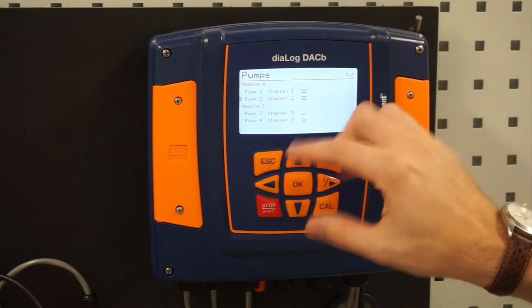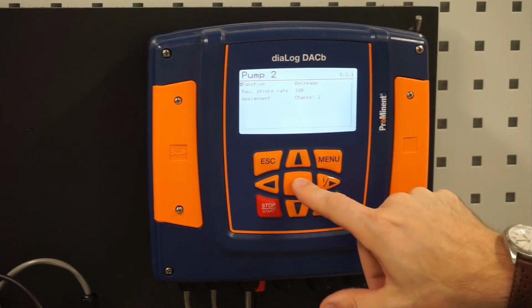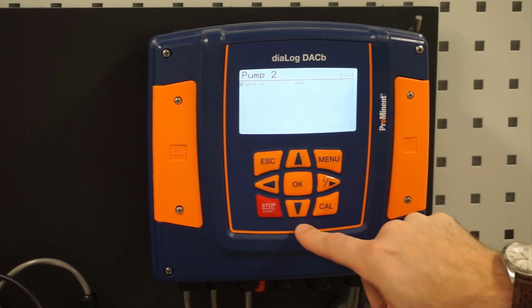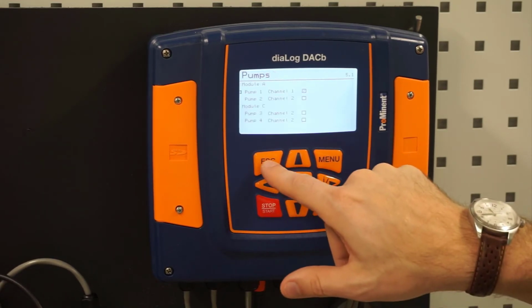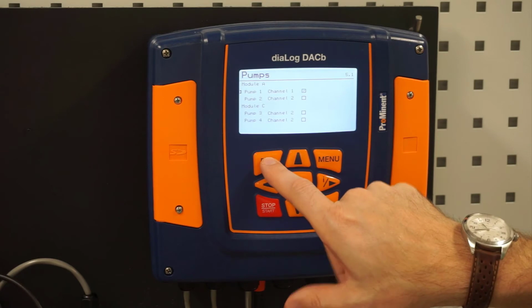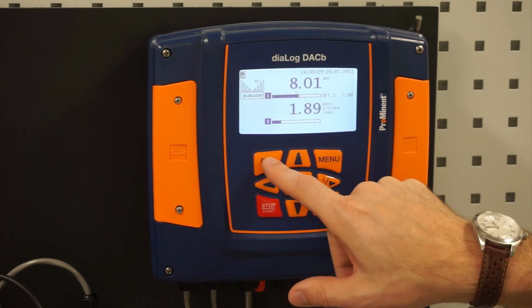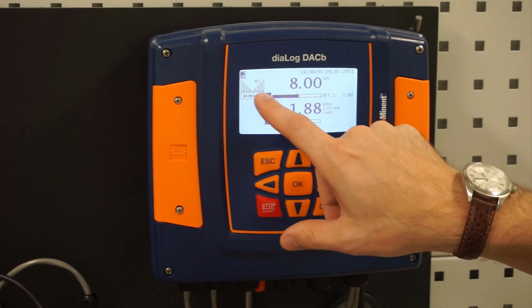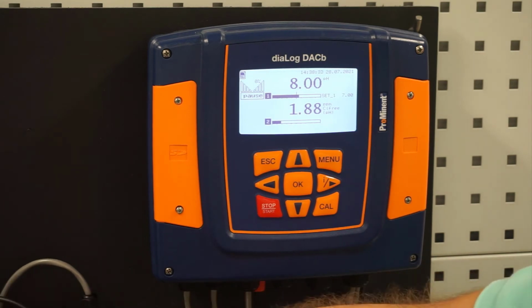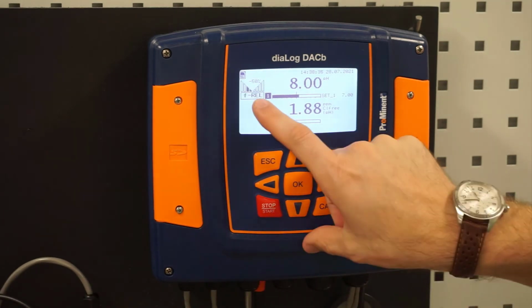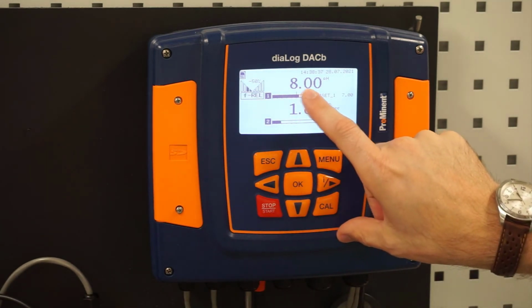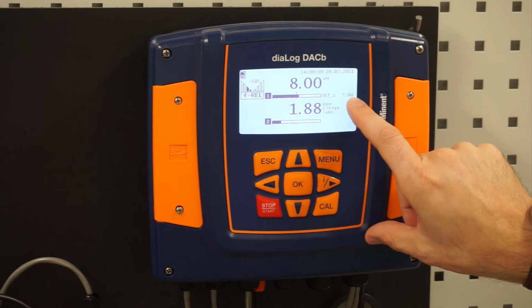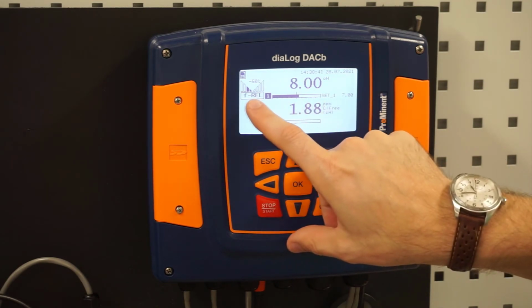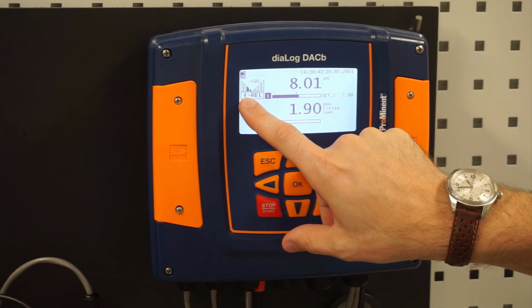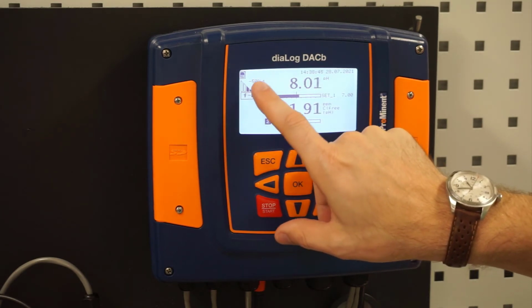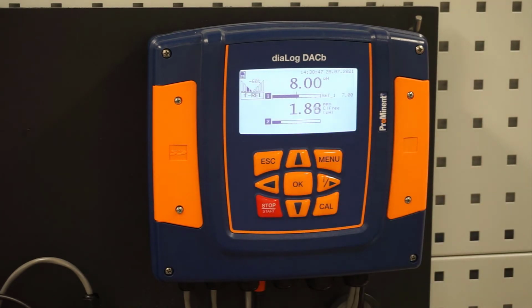If we don't have any other pumps, I can go in here and actually turn this off so that it is not displayed anymore. So if I back all the way out, you can see that we're paused, so I'm going to push down my flow just to simulate flow. Right now we're at a pH of 8. We should be at 7. So we are feeding acid with our frequency relay at a rate of 50%.